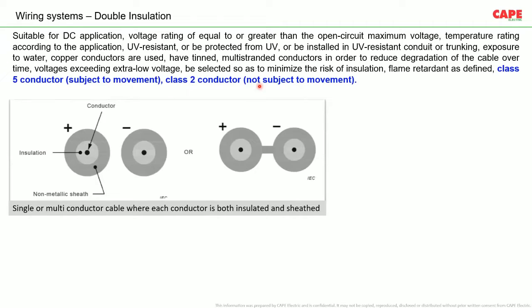The wires must have a double insulation. Say for example here, the inner conductor first has an insulation, then there is a non-metallic sheath. So this is a method to achieve double insulation. The idea is even if one insulation is broken, there is one more insulation to protect against electric shock. So these are the two types of double insulated wires which are recommended in the standard. You can see in the picture.